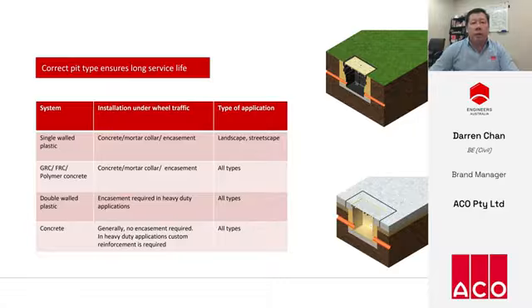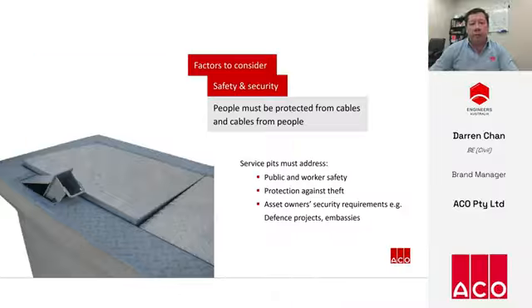An enclosure's material type and wall design can dictate where pits can be installed and whether a collar or concrete encasement is required. In general, enclosures with single thin flexible walls such as plastic pits should only be installed in light-duty areas. Where there's vehicular traffic, all thin-wall pits should only be considered as sacrificial formwork. Concrete or double-walled plastic pits, however, have good structural strength.